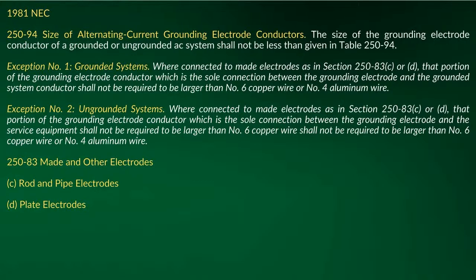And if you notice here, when you get to exception 1, we'll just do grounded systems. Exception 2 is ungrounded. It's pretty much the same thing. But what it tells you here, it says when connected to made electrodes, and then it says as in 250-83(C) and (D). When you go pick those up, that was rod and pipe electrodes and plate electrodes. Okay. Now, what you're going to see, it was at this point where we used to have made electrodes. That is no longer in there. You're not going to hear made electrodes anymore.